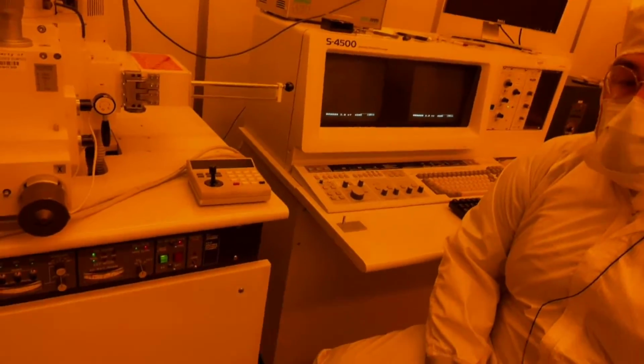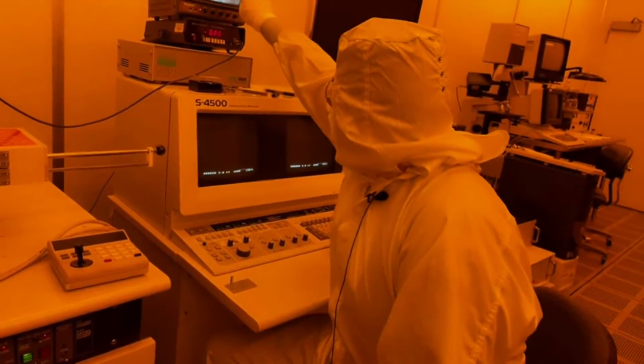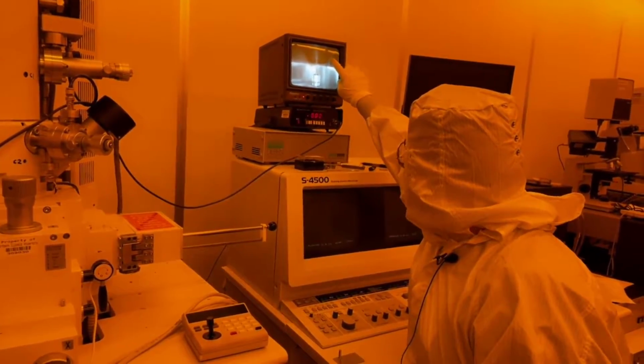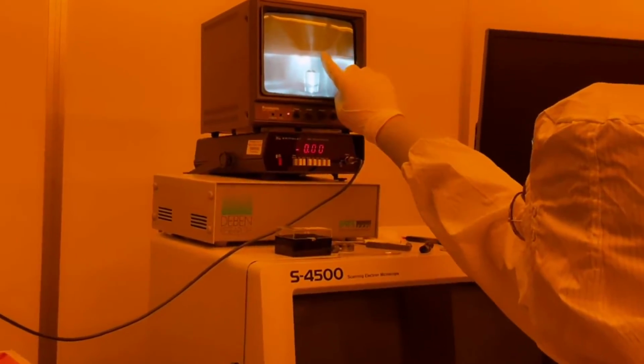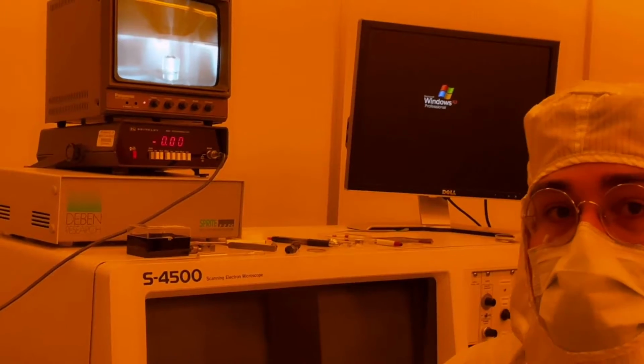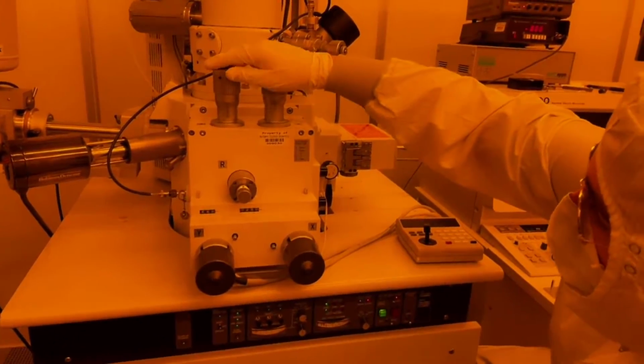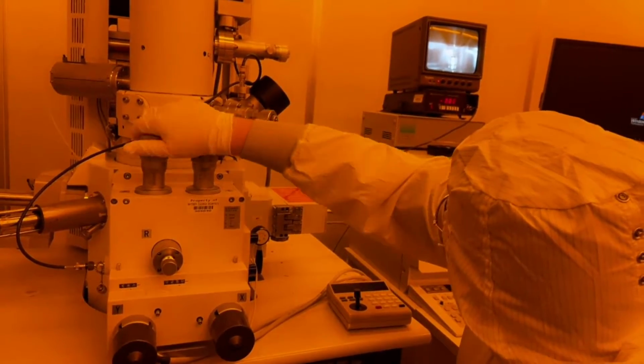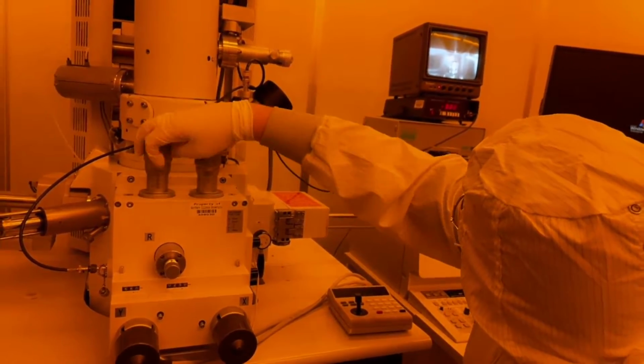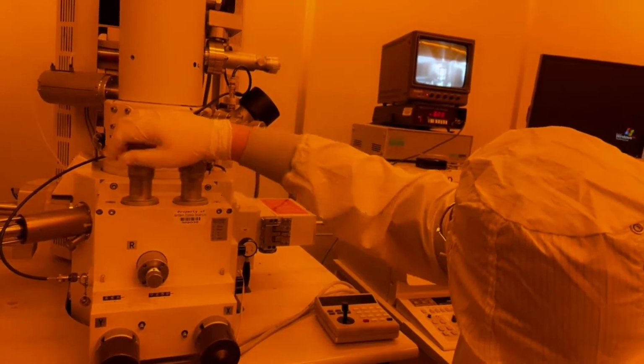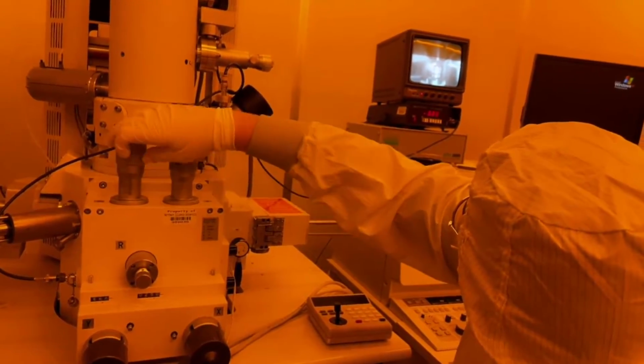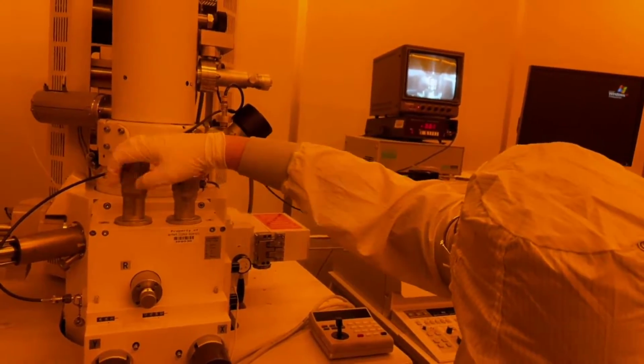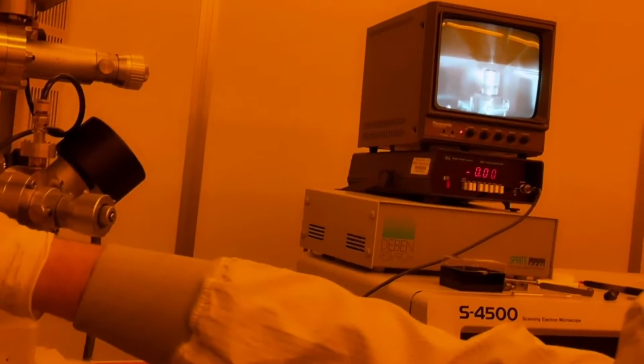Now, when you're taking images, you want to have your sample as close to the detector as you can. So up here is the detector, and if you kind of imagine a triangle being made with these two angles, if your sample can be within that area, that's where you'll get the best image from your sample. So to do that, we can control the Z height right here. So we just unscrew it up. You see it raises the sample. And we just want to put it in that area, the virtual lens. All right, that's good.